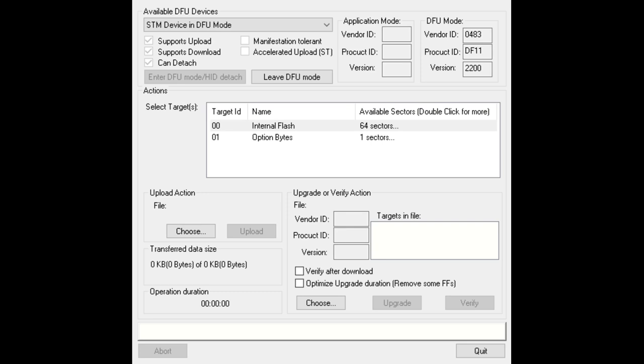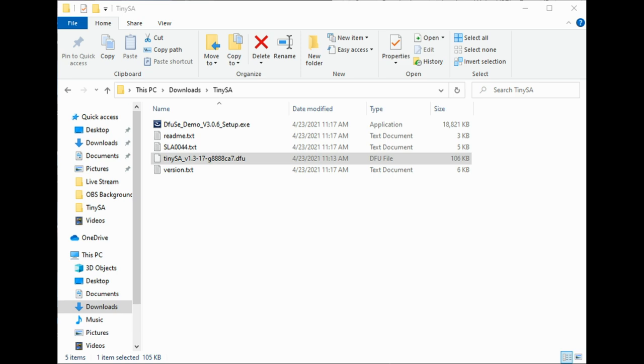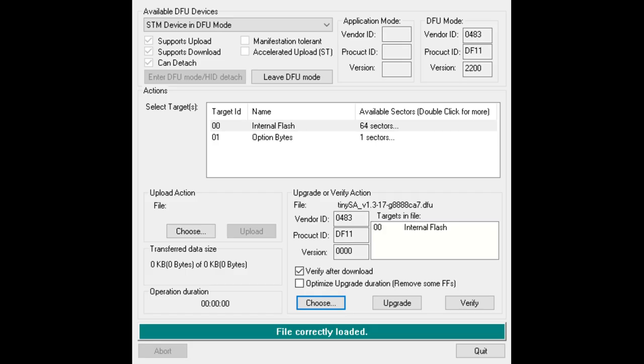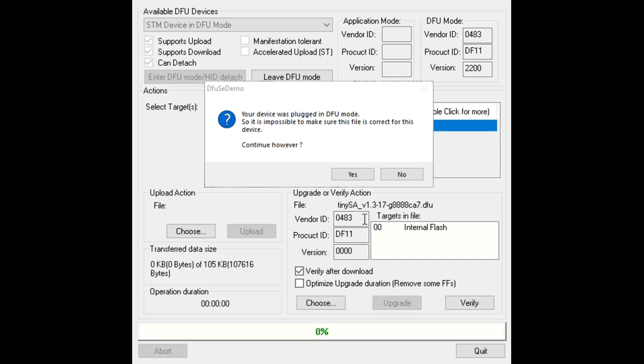Okay, so I have the software running and here I have the STM device in DFU mode and that is the only available device that I have. So what I want to do is come down here to upgrade or verify action and click verify after download, and now I am going to choose my DFU file. So I browse to the directory where I downloaded the file and it is here. I highlight that and click open. Now it says the file is correctly loaded. The next thing I want to do is click upgrade. Your device is plugged in in DFU mode. It is the correct file so I am going to continue.